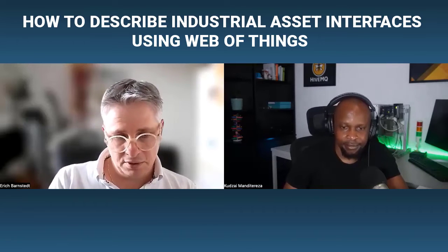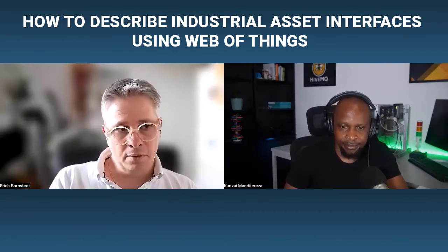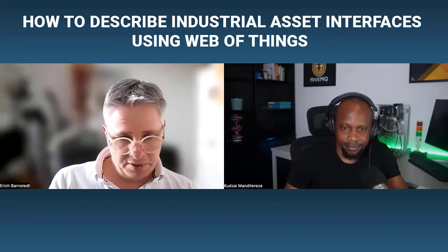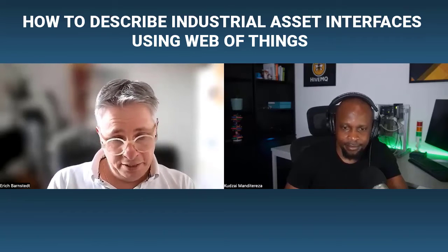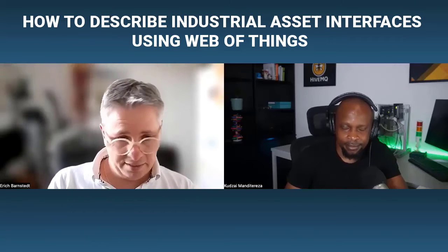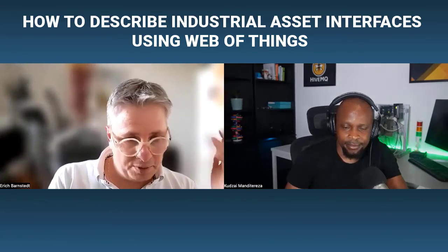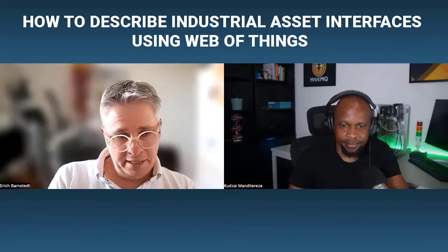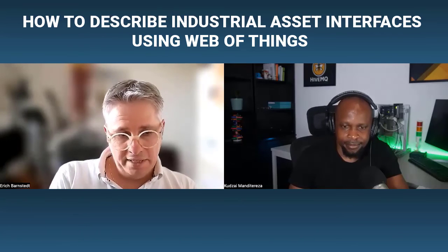And that's actually something we show together with Siemens. So you basically just add the reference to the namespace of the OPC UA information model that you want to map to, right? And then in each of the properties, including the Modbus register address and what it is and how many bits, maybe even the unit, is it a temperature in degrees Celsius, for example, you can add the OPC UA information model type information that you want to map that particular data tag to, right?